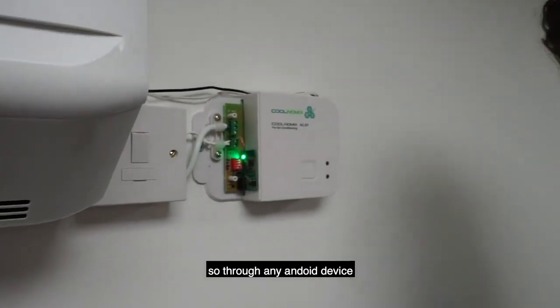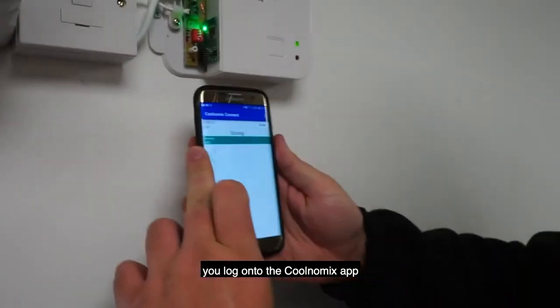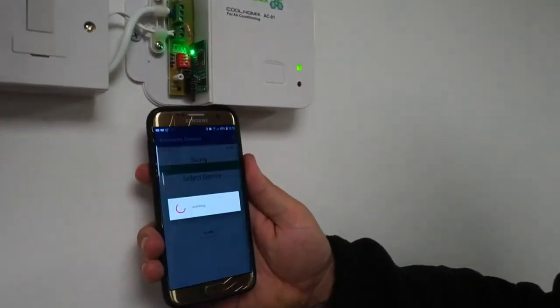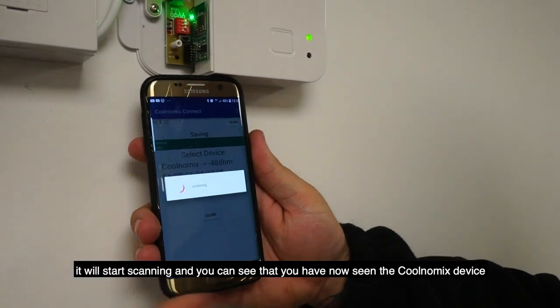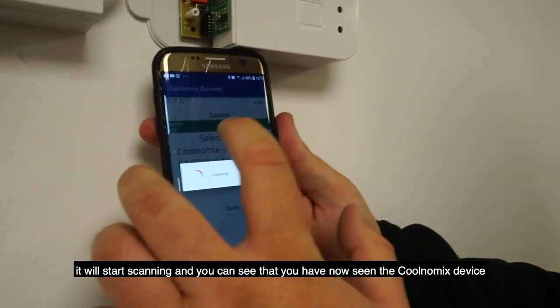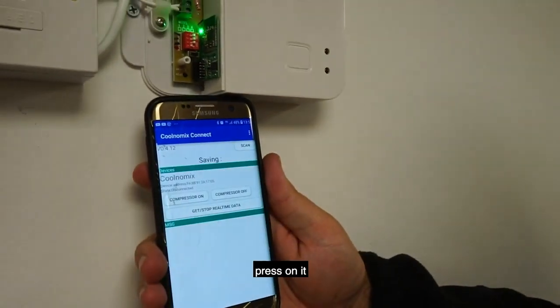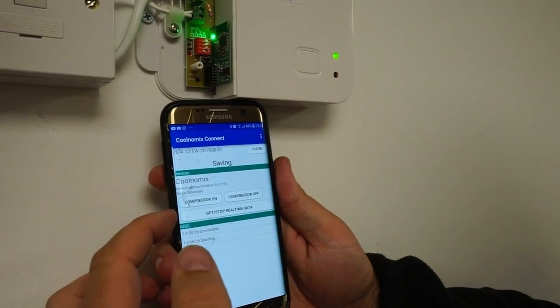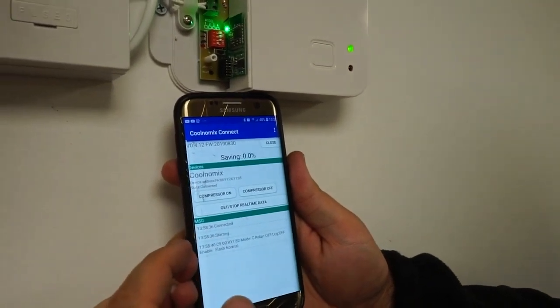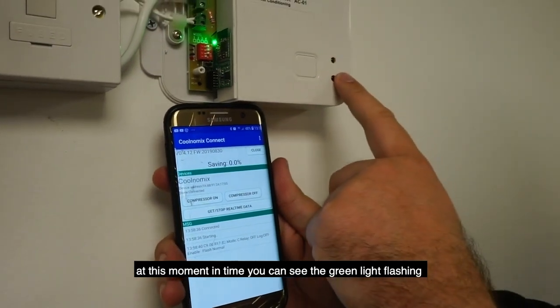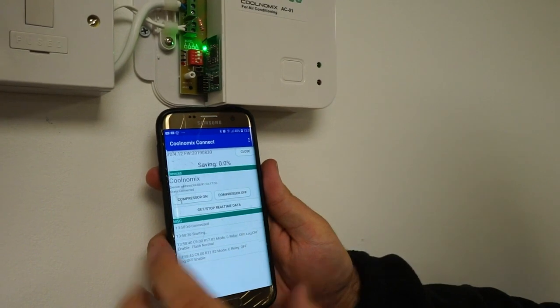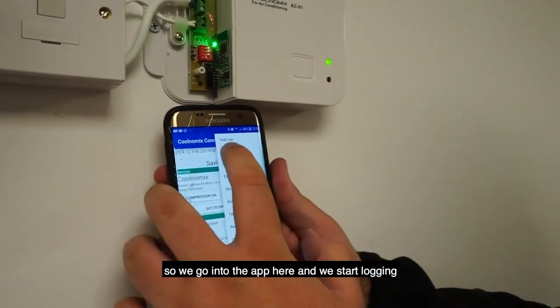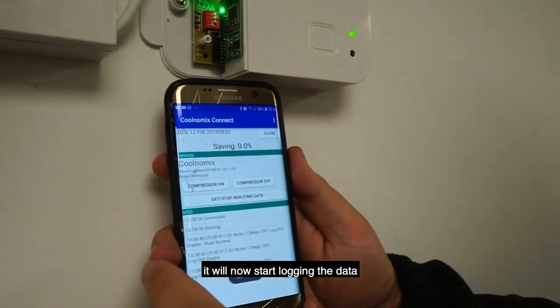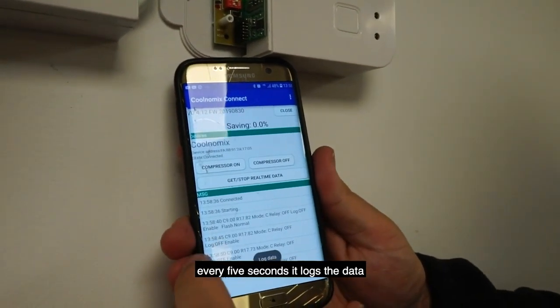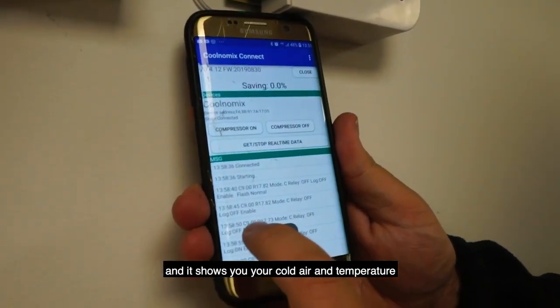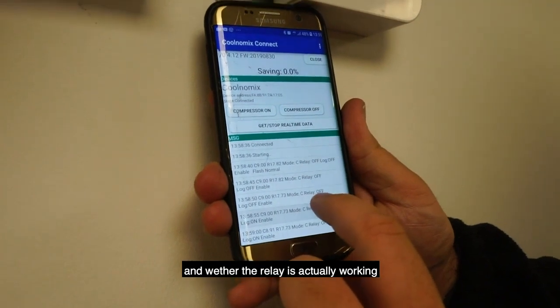So through any Android device, you log on to the Coolnomix app and you press scan. It will start scanning and you can see that you have now seen the Coolnomix device. You press on it and you can see its ID code. It's connected and starting. At this moment in time you can see the green light flashing, which means that it's still trying to get the temperature in the room. So we go into the app here and we start logging. It will now start logging the data. Every 5 seconds it logs the data, and it shows you your cold air temperature, your return air temperature, and whether the relay is actually working.